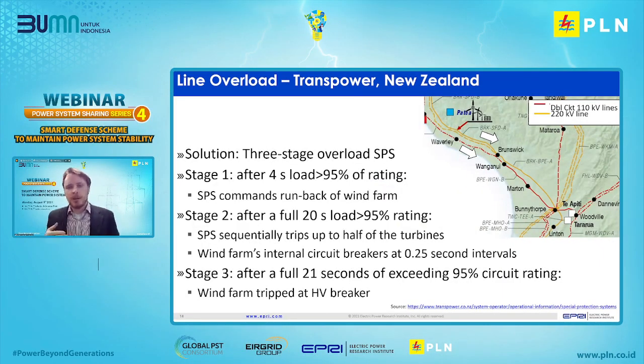The way this operates is that it monitors the flow on each of the lines, and there are 3 stages of actions. The first is that if there is an overload of greater than 95% of the line rating, a run back command is sent to the wind farm to decrease its power output. If the line is still overloaded after 20 seconds, the scheme trips up to half of the wind turbines at the wind farm site. This is where the circuit breakers on the feeders within the wind farm are tripped at 0.25 second intervals. If after 21 seconds the overload still exists, the entire wind farm is disconnected by tripping the high voltage circuit breaker on the grid side of the connection point.